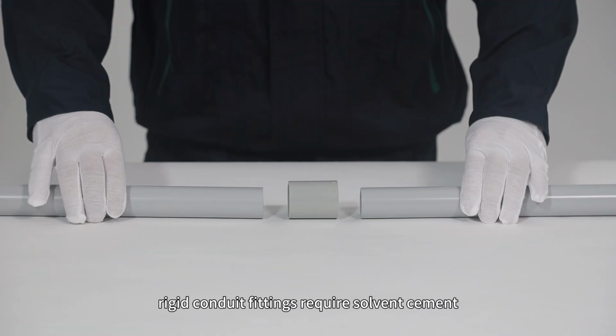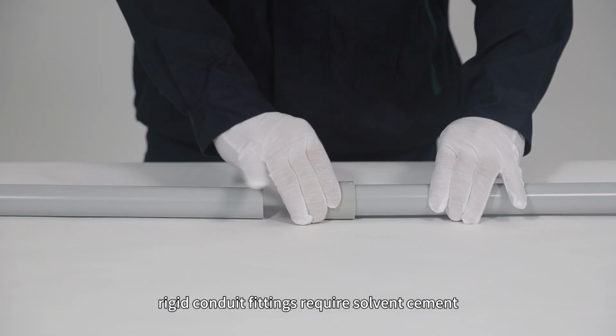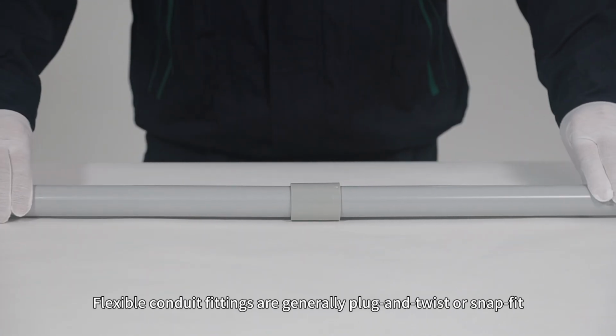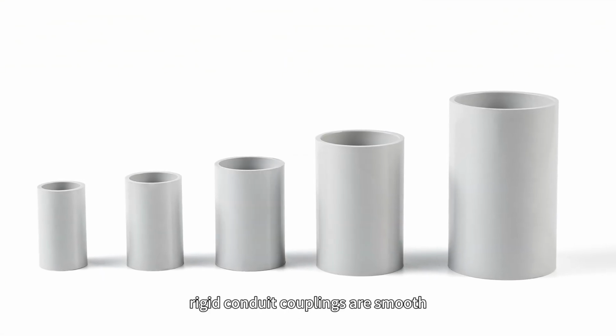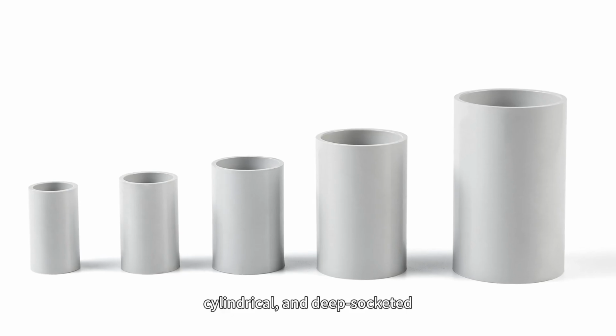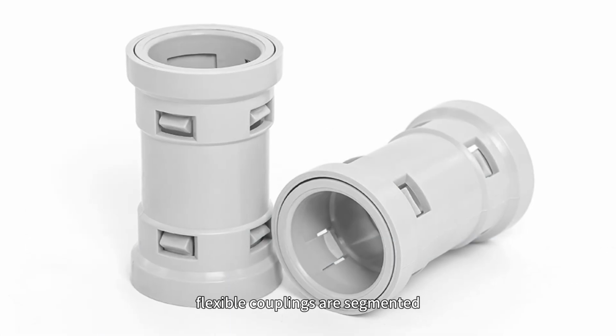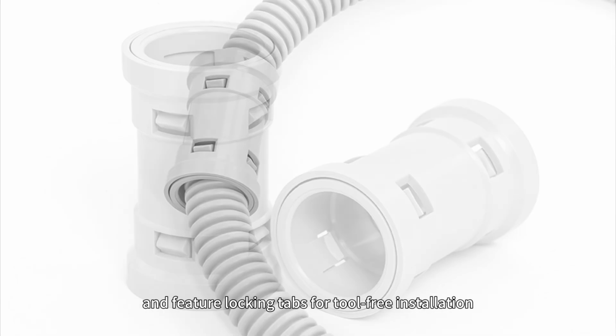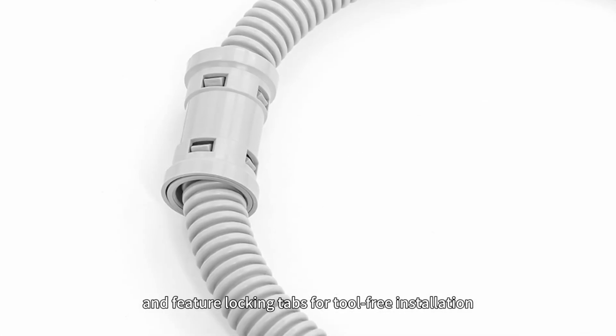Another difference, rigid conduit fittings require solvent cement. Flexible conduit fittings are generally plug and twist or snap fit. For example, rigid conduit couplings are smooth, cylindrical, and have a socket. In contrast, flexible couplings are segmented, ribbed, and feature locking tabs for tool-free installation.